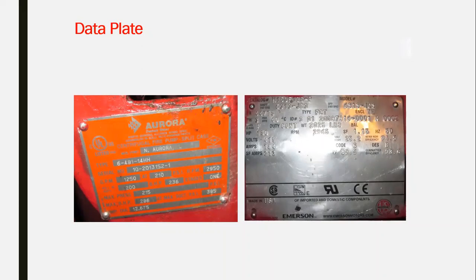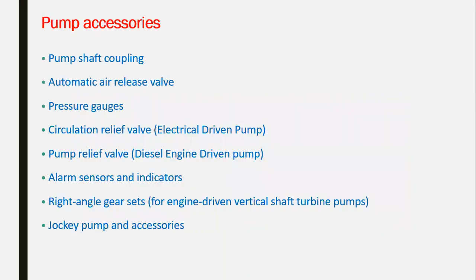Okay. So be sure to track the serial number for the fire pump. The accessories for the fire pump will be a pump shaft coupling, the automatic air release valve, and the pressure gauge, circulation relief valve for the electrical driven pump, and the pump relief valve for the diesel driven pump, alarm sensors and indicators, right angle gear set for the engine driven vertical shaft, and the jockey pump and its accessories.